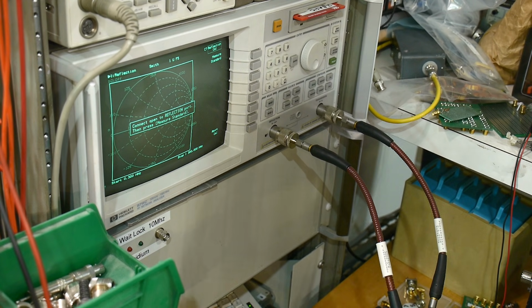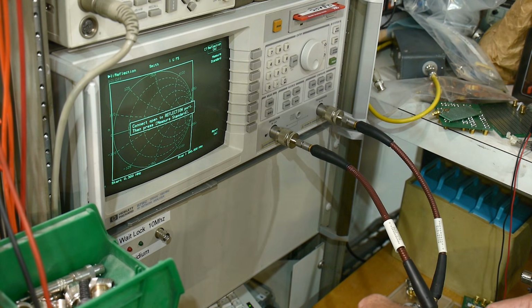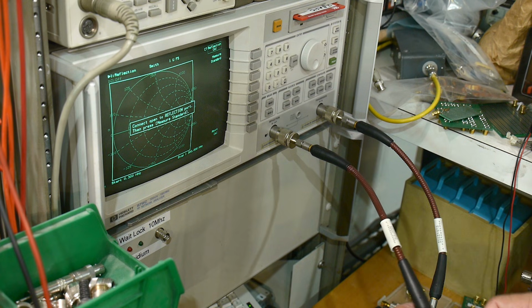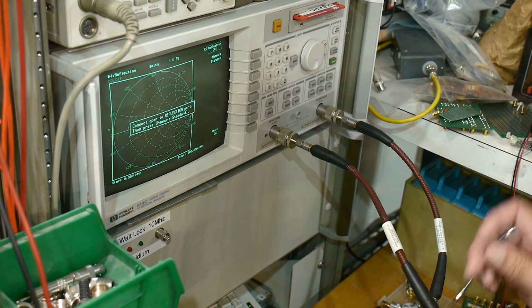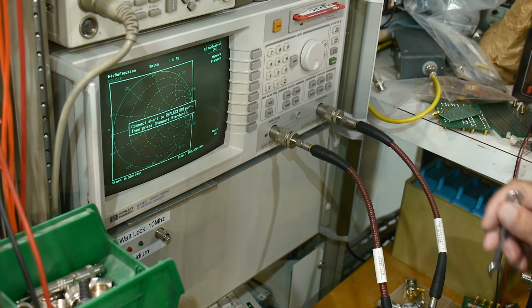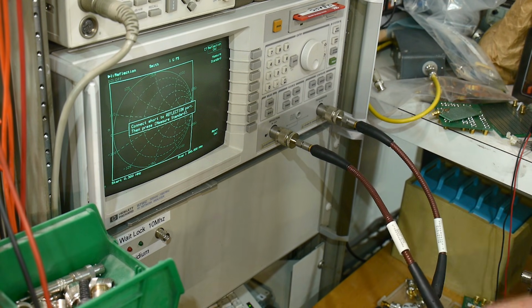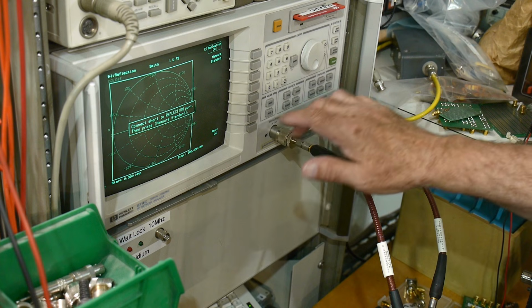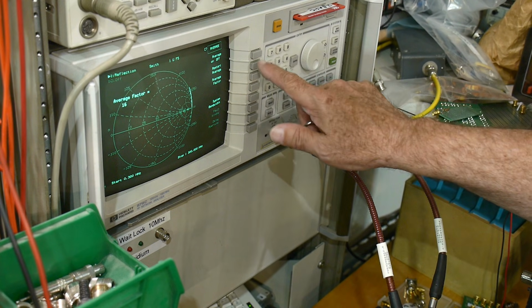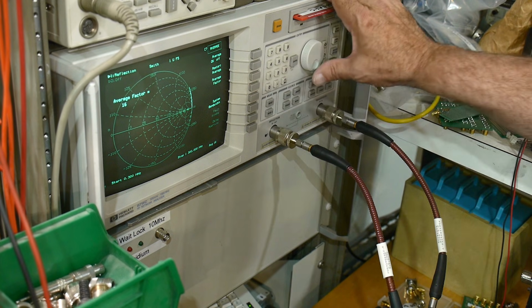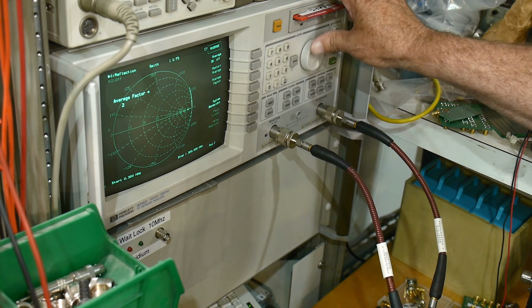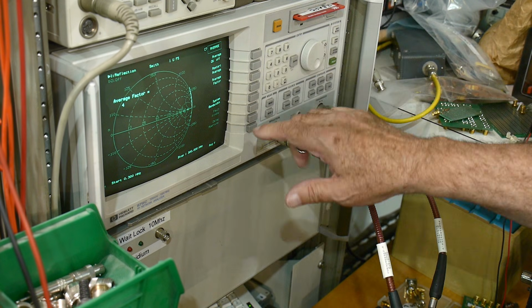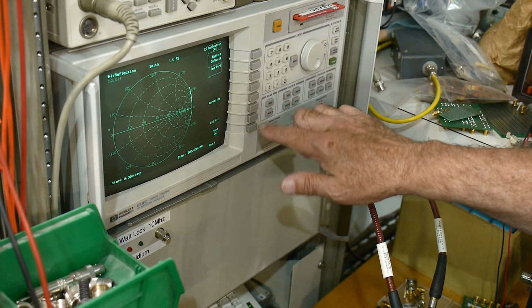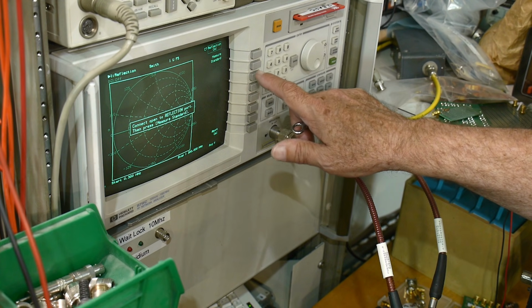Okay, so this is our cal standard. It's asking for an open, so we will attach the open. It's asking for the short. I think I lost my averaging. Let's turn averaging back on. Averaging on, with an average factor of 4. I just want to make this apples and apples. There we go. Calibration, everything looks good.